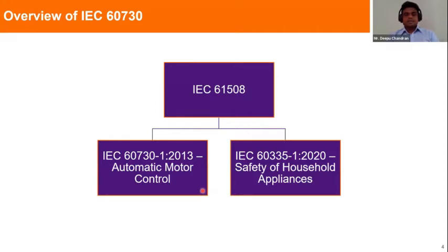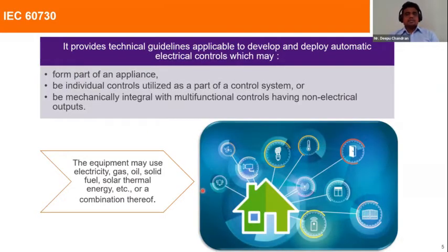So when you look at the techniques and methods that need to be applied for the software lifecycle activities, these standards have a cross-reference with IEC 61508. The detailed table on the principles that need to be applied during the planning phase, the requirement phase, the design phase, the development phase, as well as the verification phase is clearly referenced back to 61508. So I'm going to talk about the process activities by referring to these tables and give you some tips on how to automate these activities so that you can quickly develop the software, verify it, and provide evidence for its compliance with the IEC 60730 standard.